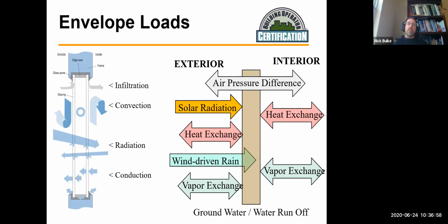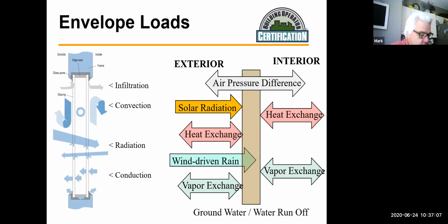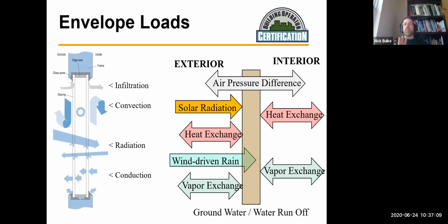So there's a key difference there, which is why I wanted to make sure that A, you need to know what your building was designed for, and B, most buildings, so 95% of commercial buildings, like a positive 0.05-ish of water column, enough to keep your doors closed, so to speak, and not push out windows, versus a natatorium where you're trying to capture moisture and not push it into your assemblies, but you're actually trying to exhaust it out of the building.